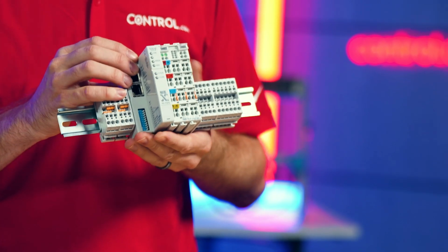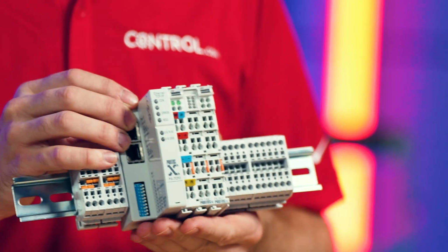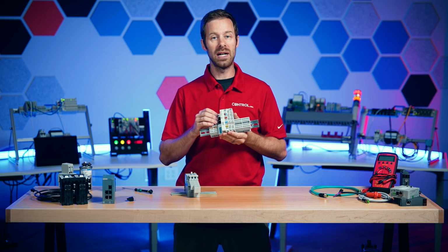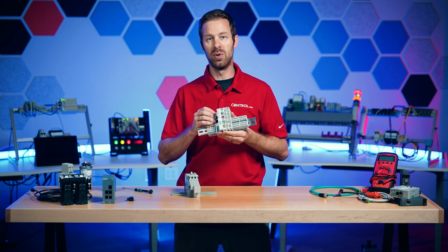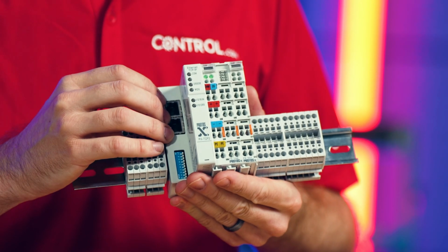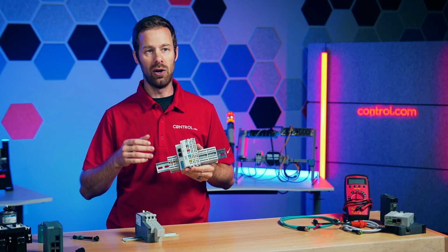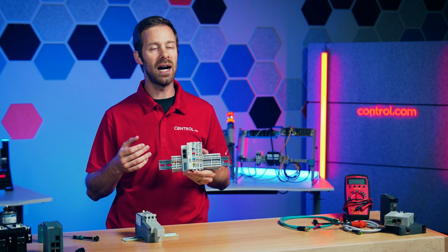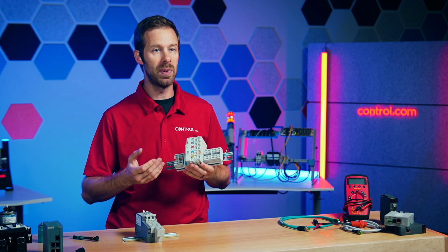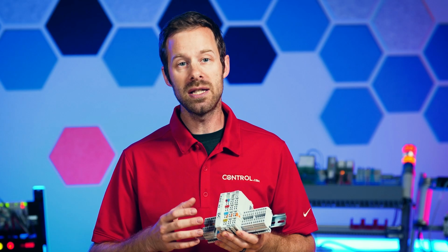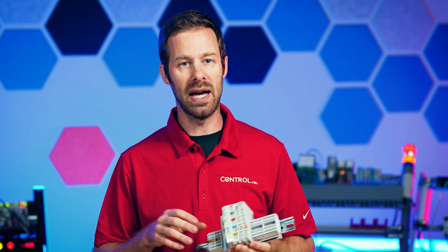Now, they look a little bit different because they don't contain a processor, but we see many of the familiar things that we would see on any modular control system. First, we have what's called a network adapter or a network bus module. These will have different communication ports, sometimes Ethernet, EtherCAT, RS-232, RS-485, and they'll have communication capabilities like Ethernet IP, Modbus over TCP, all kinds of network abilities to be able to share that information.